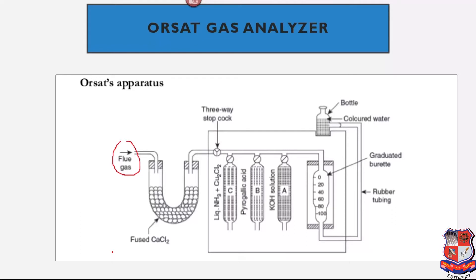We need to analyze how much CO, CO2, O2, and N2 are present in the flue gases, and from the analysis results we predict or optimize the process. If exhaust gases contain a larger content of CO, it indicates incomplete combustion. With complete combustion, there is a larger amount of CO2. If there is excess O2, it indicates a larger amount of oxygen was provided. Ultimately, by analyzing the results, we can optimize the process.